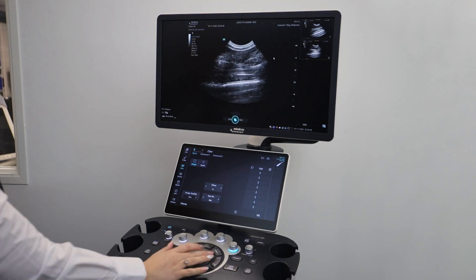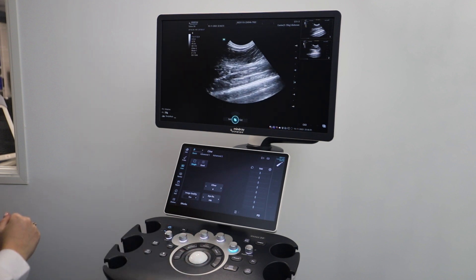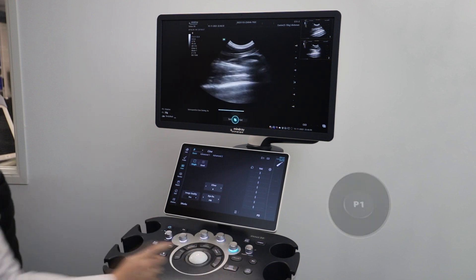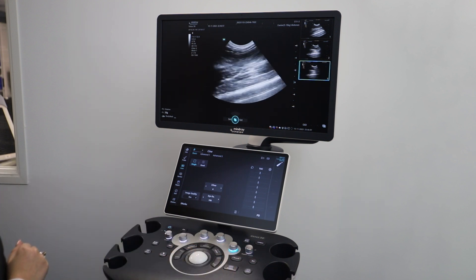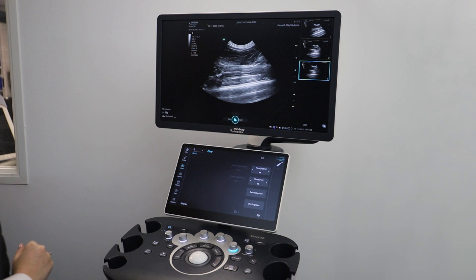Once you're happy, you can go back to scanning and the cursor will disappear. To save a cine loop, press P1 and it will save a six second retrospective video. Should you wish to extend this, it can be done in the scanner settings.